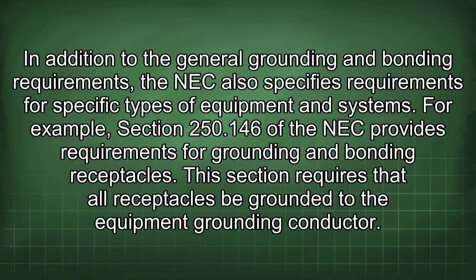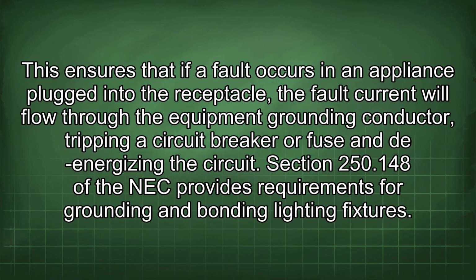In addition to the general grounding and bonding requirements, the NEC also specifies requirements for specific types of equipment and systems. For example, Section 250.146 of the NEC provides requirements for grounding and bonding receptacles. This section requires that all receptacles be grounded to the equipment grounding conductor. This ensures that if a fault occurs in an appliance plugged into the receptacle, the fault current will flow through the equipment grounding conductor, tripping a circuit breaker or fuse and de-energizing the circuit.